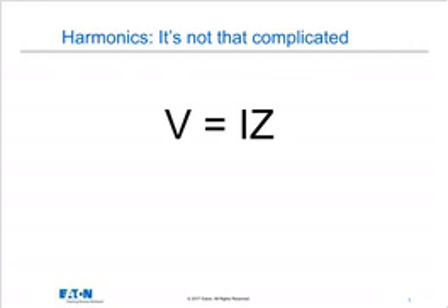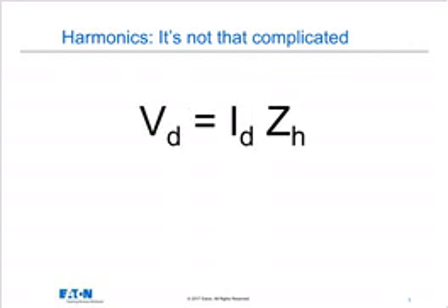But then the loads that we put in the system used to all be 60 hertz loads, and the impedance of the load comes into play, and we look at voltage drop along the line with the impedance of the lines. But nowadays what we have to consider is the same Ohm's law, but think about it flowing from the opposite end. Think about the current coming back from the loads. And the more current that we add in terms of current distortion, the more that we actually cause heating problems and other load-related issues throughout the system.